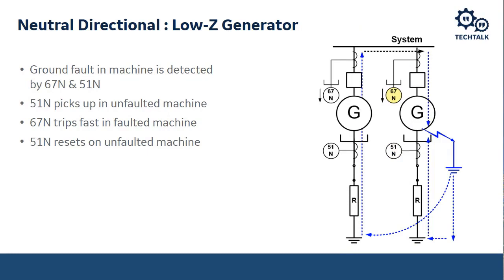So the ground fault in the machine is detected by either the 67N or the 51N. The 51N picks up in the unfaulted machine. The 67N trips only fast on the faulted machine. Then the 51, the faulted machine, trips, the 51N resets on the unfaulted machine, and we go back to normal, allowing the unfaulted machine to stay in service.